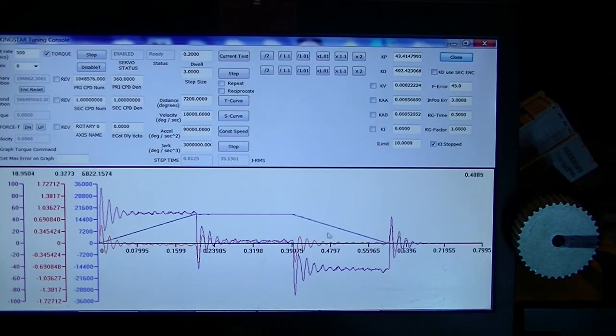So what we have here is a well-tuned servo loop, but we think we can do better. First of all, these edges are very sharp, and you can see it is commanding a great deal of current at this point, 90%. So these changes are very, very abrupt, and I don't know if you can hear it, but there's 4 individual bumps that you can hear while you're running this, and it happens to be these 4 peaks.